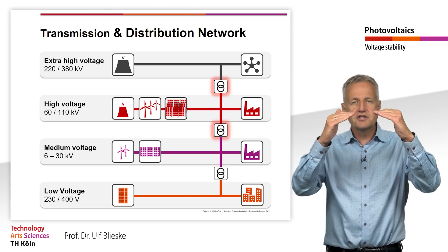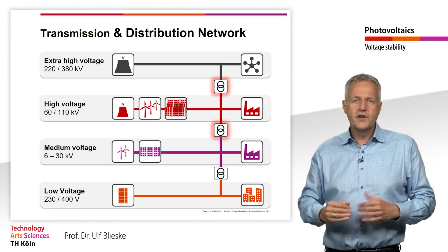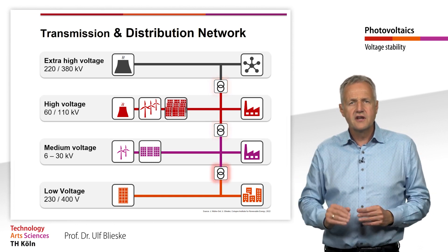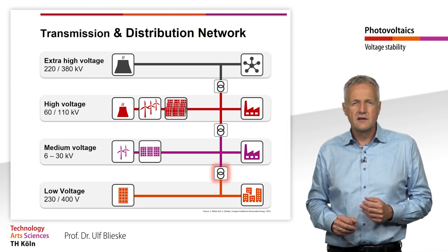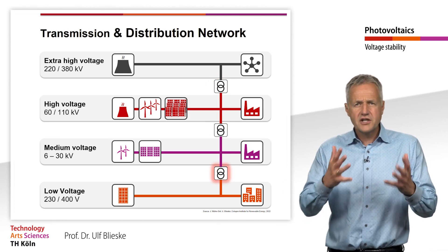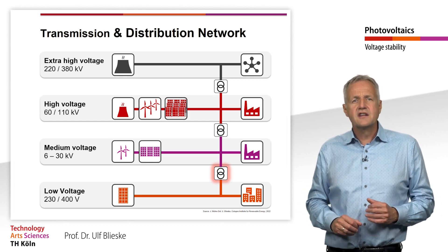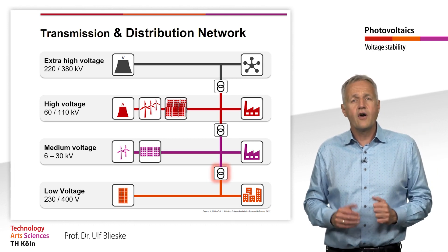Only between medium voltage and low voltage, a fixed transformation ratio is given usually. Due to the fixed transformation ratio, the voltage on the low voltage side changes with the voltage on the medium voltage side of the transformer.